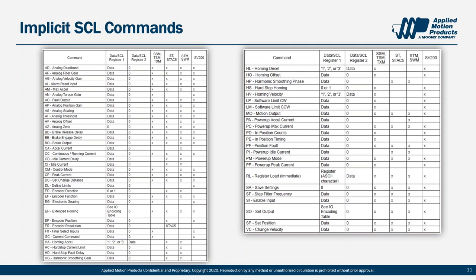The Host Command Reference details each SCL command supported in implicit messaging and how to use them. For a complex move such as hard stop homing, you would need to send about a dozen SCL commands to set up all the different move parameters — speeds, currents, and so on — before finally kicking it off with an HS command. While implicit messaging is easier than explicit messaging, it's still quite an ask to do all that PLC programming and sequencing. That is exactly why we've created our AOIs — we want this to be as accessible and easy to use as possible.